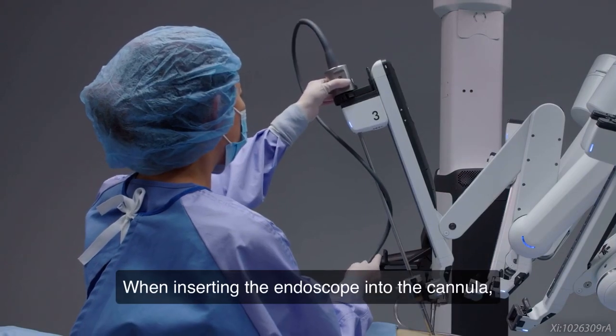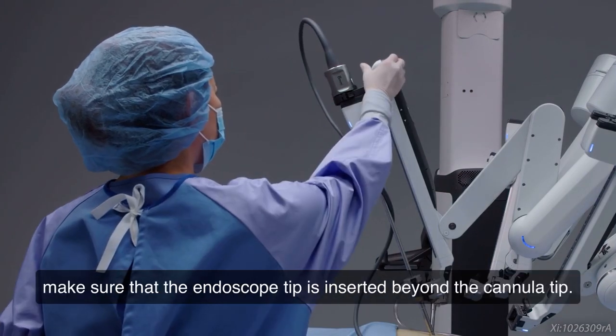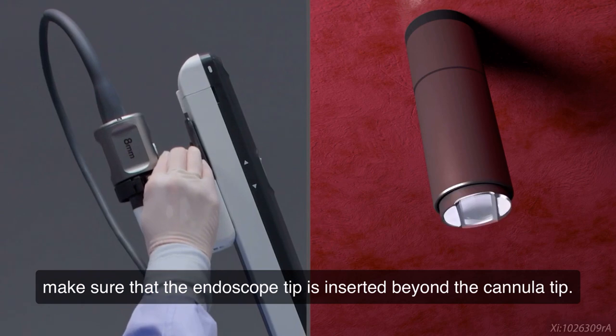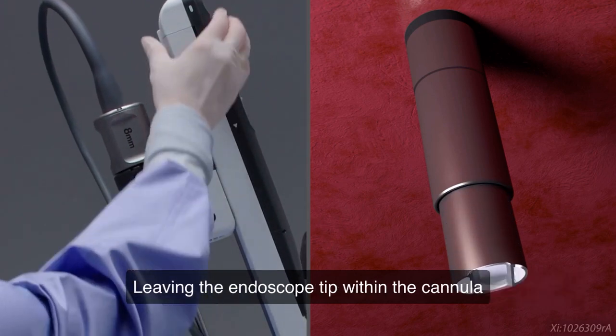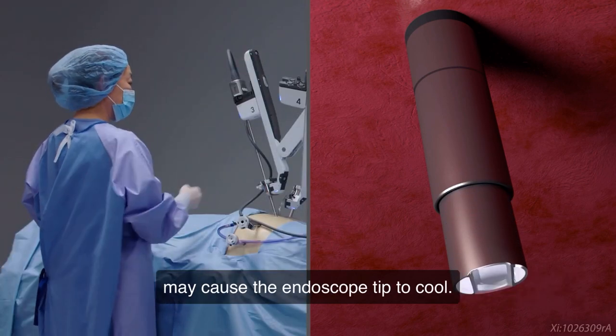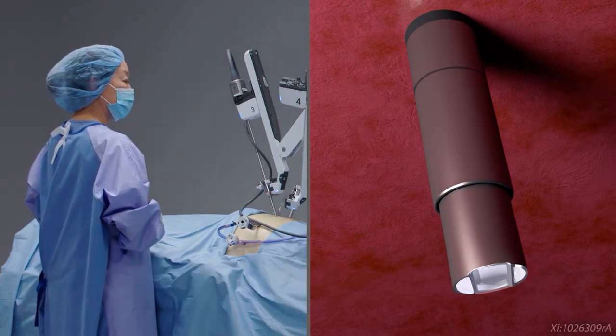When inserting the endoscope into the cannula, make sure that the endoscope tip is inserted beyond the cannula tip. Leaving the endoscope tip within the cannula may cause the endoscope tip to fog.